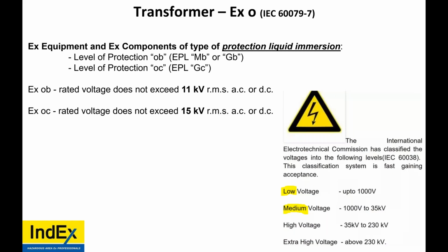When we talk about EXO transformers, to the standard IEC 60079-7, we're talking about protection via liquid immersion, to Ex ob or oc. So EPLs: GA, GB, GC. We're specifically talking about GB and GC, so zone 1 and 2. For OB, it can only go up to 11 kV RMS, and OC can only go up to 15 kV. So we are only talking about low or medium voltage transformers or other EXO devices such as switchgear. It will never be high voltage or extra high voltage as per the standard.